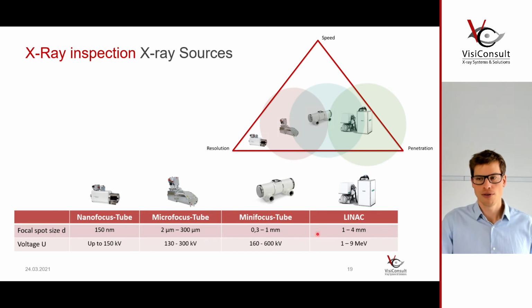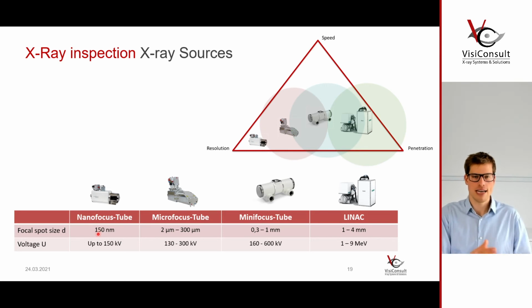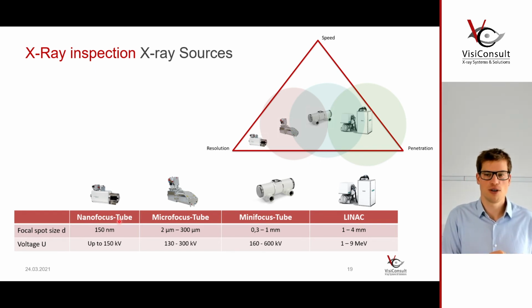And the more you go to the right, the more energy do these devices have, and you need energy to penetrate the parts. So if you have very thick walls, if you have very high density parts like Inconel, steel, you need a high energy. If you have very thin and small parts with low weight or low density material like aluminum, maybe titanium, you can go with lower energy. Of course, plastics, right? This is a piece of cake for X-ray. But we have this downside between high energy and resolution. The names nano, micro, mini already name it. You are increasing the resolution as you go towards a smaller energy and a smaller focus spot.